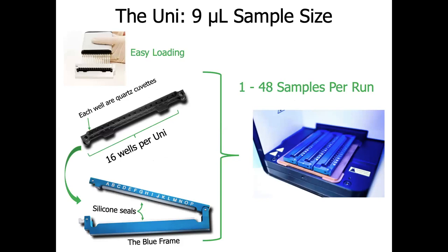The sample holder for the UNCLE is called the UNI. The UNI contains 16 microcuvettes, which each holds 9 microliters of sample per well. The spacing between the wells is the same as a 384-well plate, so you can use a multi-channel pipetter to load the samples. Once the samples are loaded into the UNIs, they are clamped in between the blue frames, which have the silicone seals. Once completely closed, it is completely sealed, minimizing evaporation during thermal ramping. Additionally, as you're working with infectious material or viruses, it does not touch the actual instrument, minimizing any exposure. You can load up to three UNIs, allowing you to run up to 48 samples at a time.